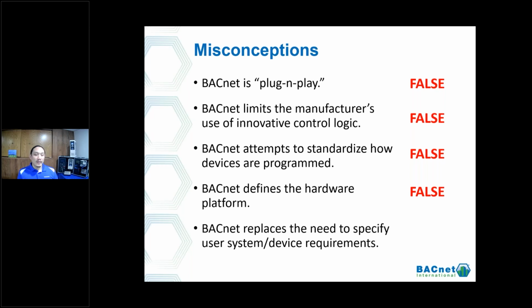BACnet doesn't replace the need to specify user, system, or device requirements. You still need to define how your system works. BACnet is just that protocol, the way to get information from one point to another, how information is exchanged out there. It's not going to tell you all the details.